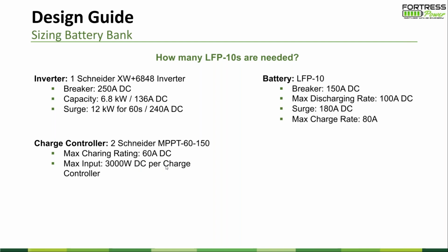For the inverter, we use the XW Pro version, which has 6.8 kilowatt rated power and surge power of 12 kilowatt for 60 seconds. We also calculated the current for you: 136 amps in the normal case, and surge power case is 240 amps. We also have 2 charge controllers where Jeremy is pointing, MPPT 60-150. For the battery specification, the breaker is 150 amps DC, max discharge rate we recommend is 100 amps which is 0.5C, surge power is around 180 amps for a few seconds, and max charge rate is 80 amps.